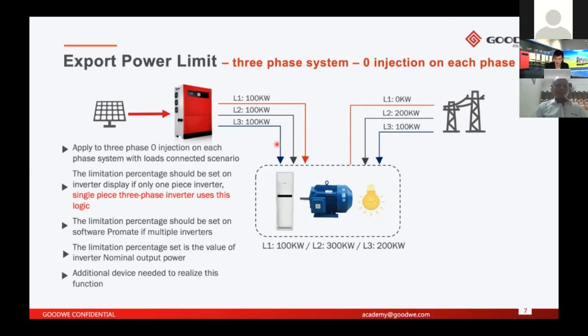So in this case, with zero injection on each phase, the inverter will output according to the lowest consumption on one phase. Like phase 1 is 100, phase 2 is 300, phase 3 is 200. So the inverter will only output 100 on each phase to make sure the loads only get the power from the grid and do not feed power to the grid. So that only happens in certain countries like the Czech Republic.